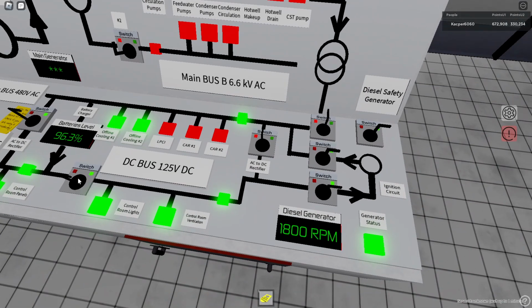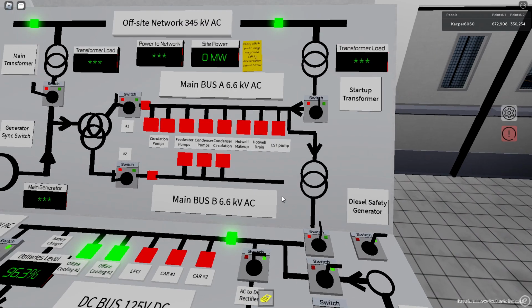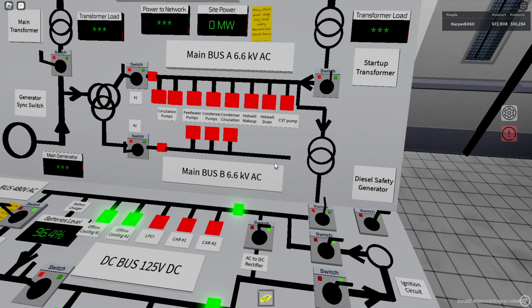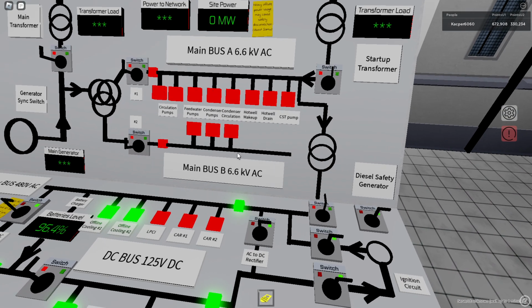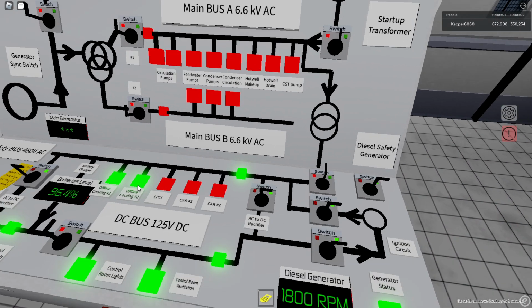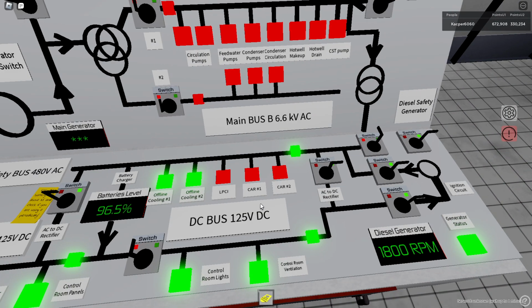And now you don't have to use battery power anymore. You can use this, and now you're basically using the starter transformer, but you don't have power in the top half, the main pumps, and you just have power down there in the emergency bus, like condenser air removal, both of them, LPCI, offline coolings.